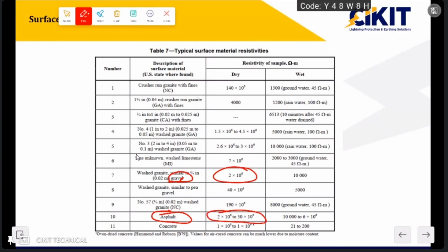Depending upon the site requirements, in some areas we will have very little space for the earthmat design. If I have very little space, another option for reducing the impact of step and touch voltages is that we can either increase the surface layer thickness, or use materials which have higher resistivity values. So if gravel is not sufficient, then in those cases we can go for either asphalt or concrete, which have much higher resistivity values.